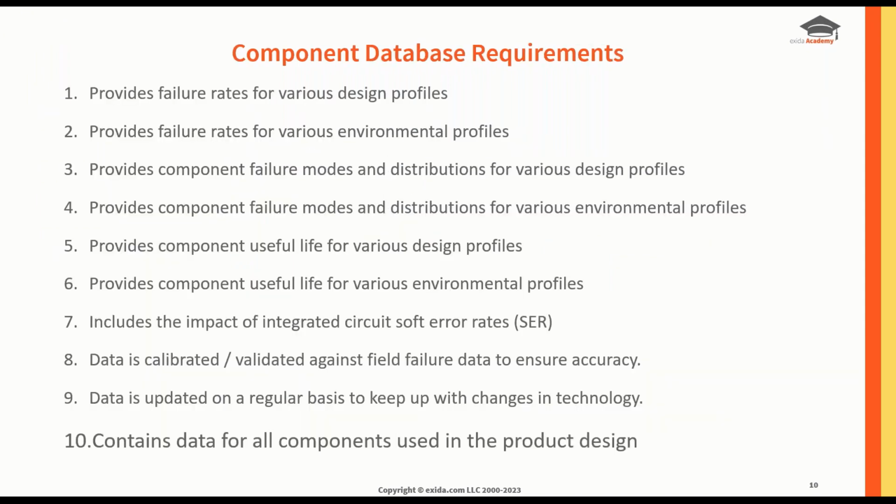You may want to develop your own database, or you may be looking to use a proprietary database, but what do you look for? What are the key requirements for this database? The database needs to provide failure rates for various design profiles and environmental profiles. It also needs to provide component failure modes and distributions for various design profiles, and again for environmental profiles. One key element is that it needs to provide the useful life for both design profiles and environmental profiles.